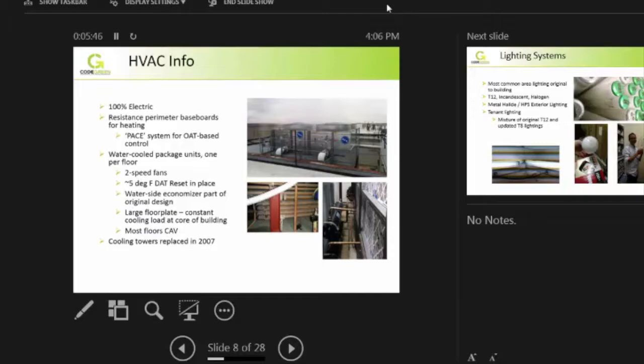Most floors were CAV, but tenants, as they've been fitting out their floors, always had the option of going to VAV, so it was a combination when we got to the building. About the only more modern component of this building that was in place is the cooling tower system, which I show there. That was working relatively well, but still hooked up to a condenser loop that has 3-way valves and no VFDs on the pumps. So even there was plenty of opportunity.